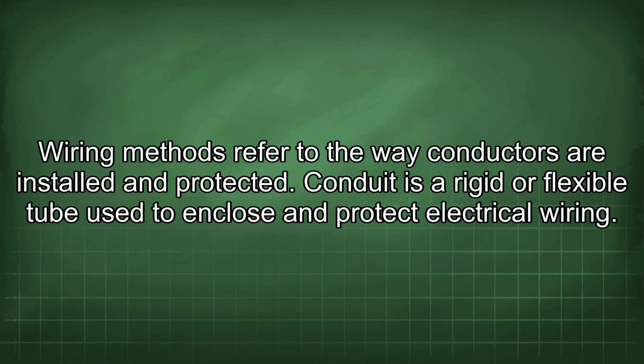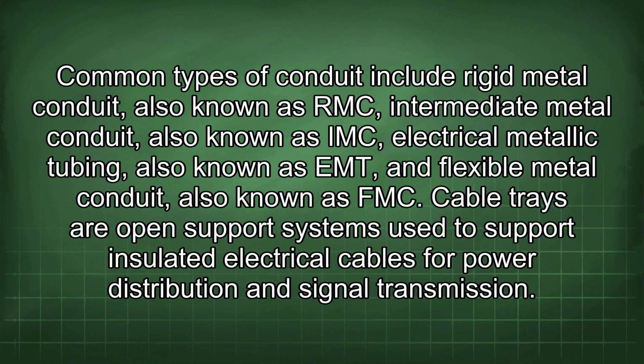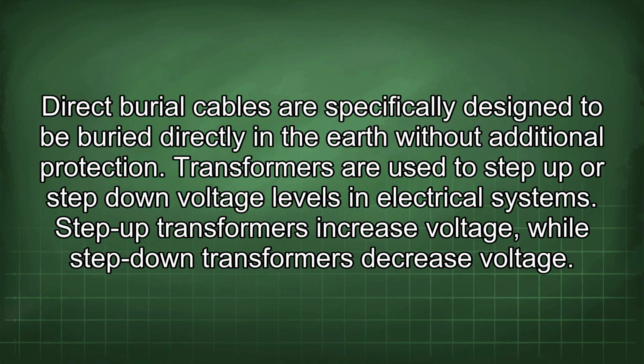Wiring methods refer to the way conductors are installed and protected. Conduit is a rigid or flexible tube used to enclose and protect electrical wiring. Common types of conduit include rigid metal conduit, also known as RMC, intermediate metal conduit, also known as IMC, electrical metallic tubing, also known as EMT, and flexible metal conduit, also known as FMC. Cable trays are open support systems used to support insulated electrical cables for power distribution and signal transmission. Direct burial cables are specifically designed to be buried directly in the earth without additional protection.